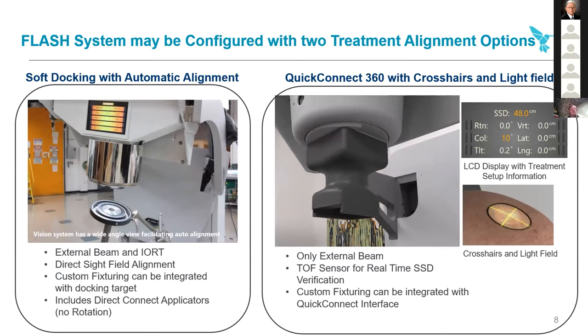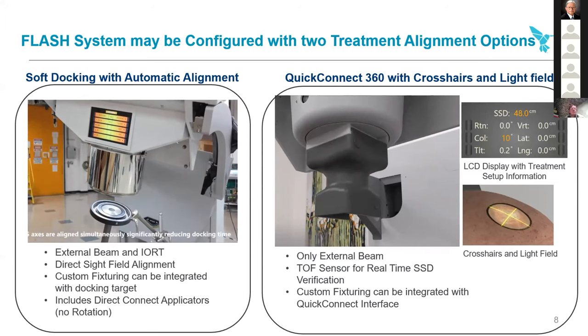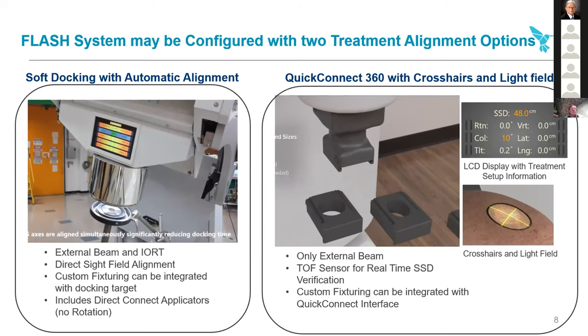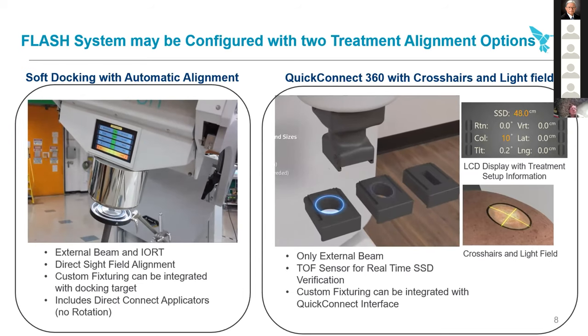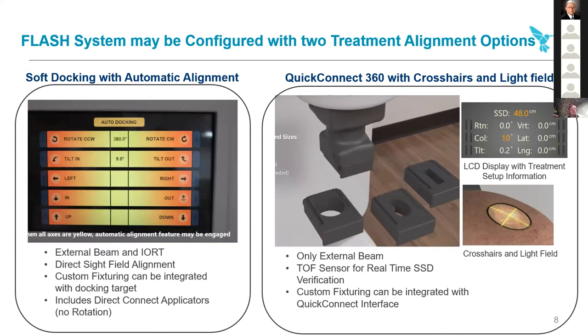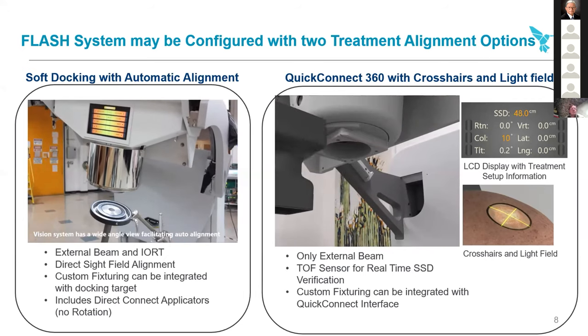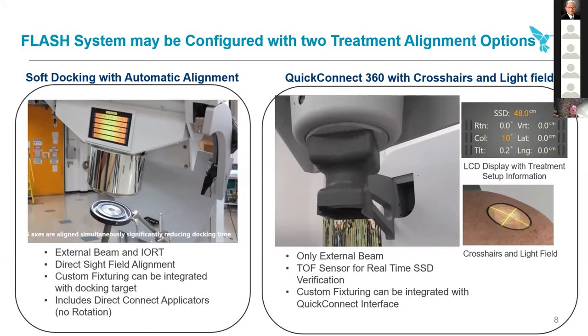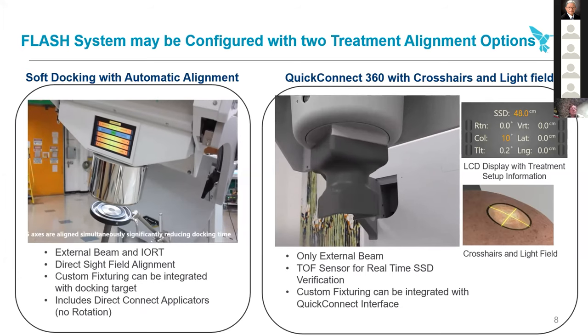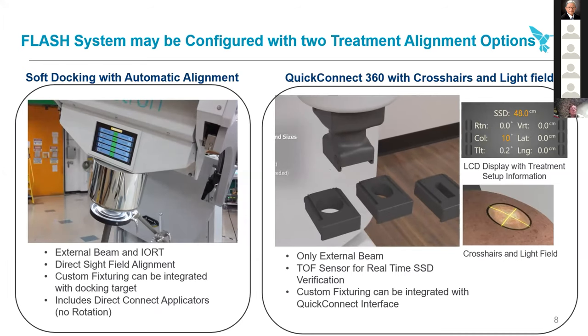When you choose one of these two platforms — the IORT on the left or the superficial derm on the right — you basically have to choose the collimation system you want to use to deliver the electrons. On the left, you see the system automatically docking itself to known fiducials on the top of the collimator flange in an IORT setup. On the right, you can see the typical superficial collimation system, we call it the Quick Connect 360, with modern upgrades for optical time-of-flight distance measurements, various shapes, modernizing what is an old clunky electron system on a large-format IORT.